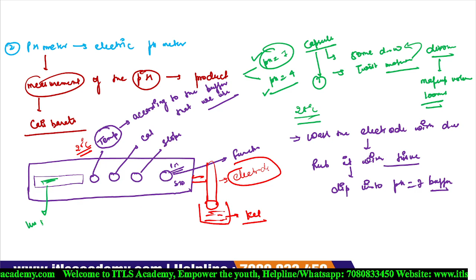Move the cal knob in a clockwise direction. When you move this knob, then the value increases and reaches 7. Till it reaches 7, you have to keep moving that cal knob, then stop. Now your pH 7 is calibrated. Again, you have to switch off the pH by moving the function key from the pH to the standby. Then again wash the electrode with the distilled water and rub it with the tissue.